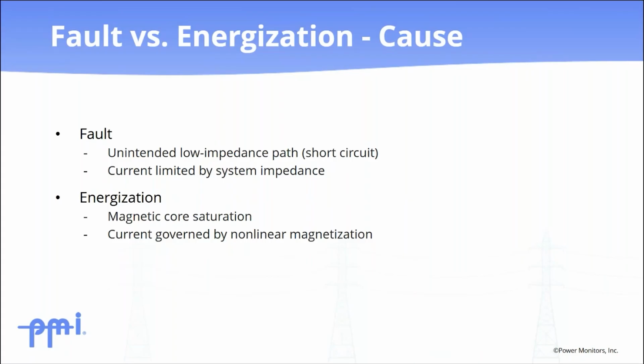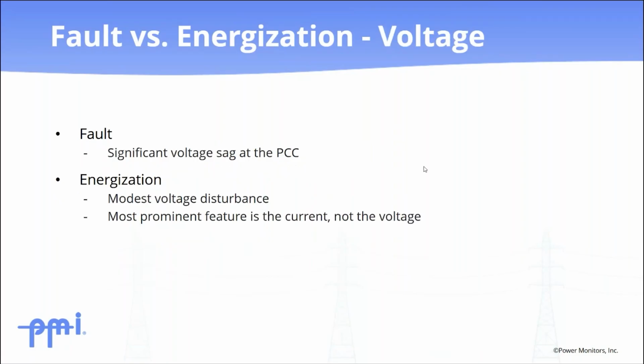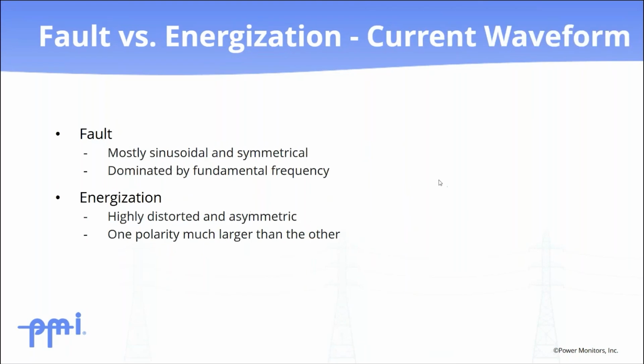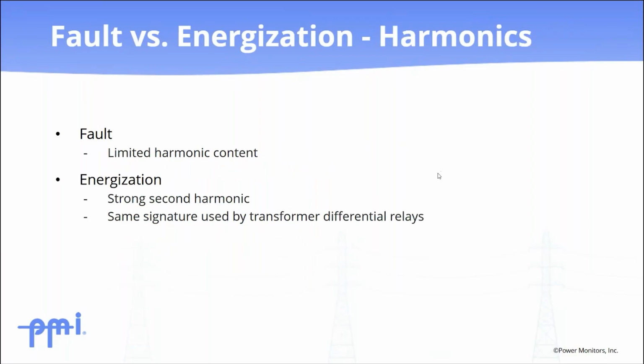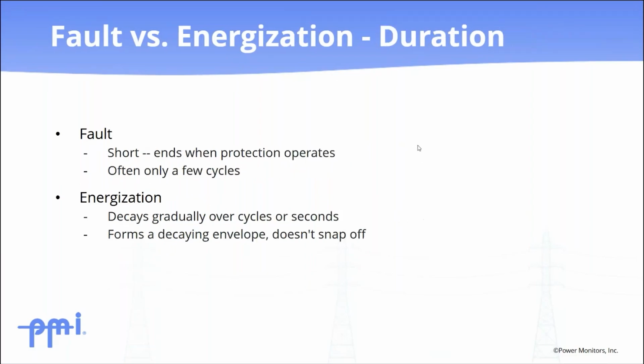A fault happens when an unintended low impedance path forms in the system, like a phase to ground or phase to phase short. Current rises rapidly, limited by system impedance. You'll get a significant voltage sag at the point of common coupling, or PCC. This current waveform stays mostly sinusoidal and symmetrical, especially in the first few cycles before protection operates. Harmonic content is generally limited, and the duration is short. Protection isolates it in a few cycles.